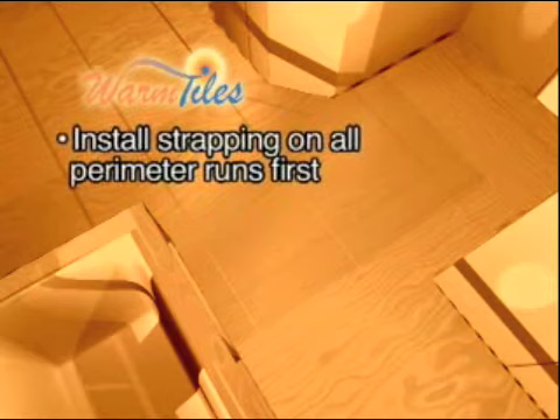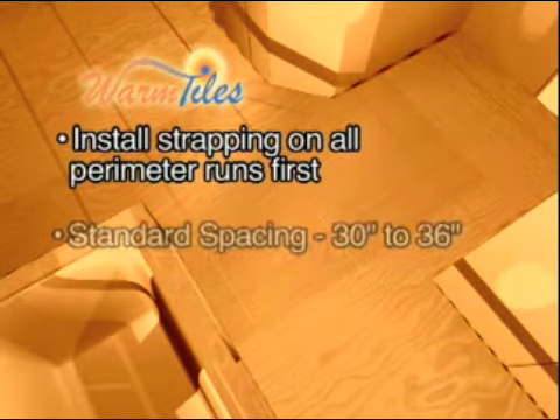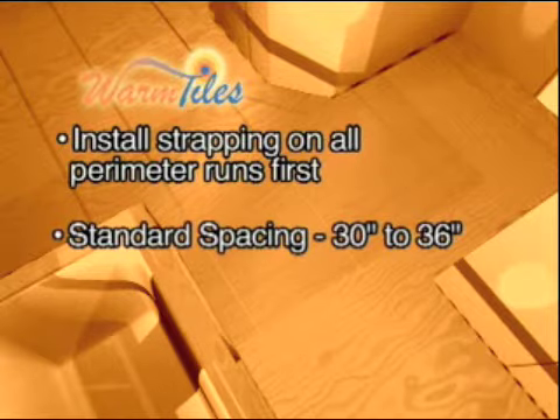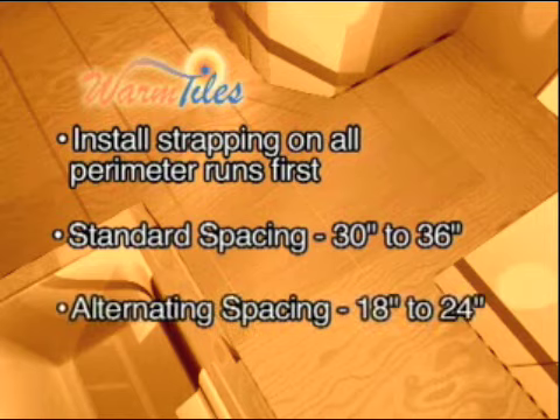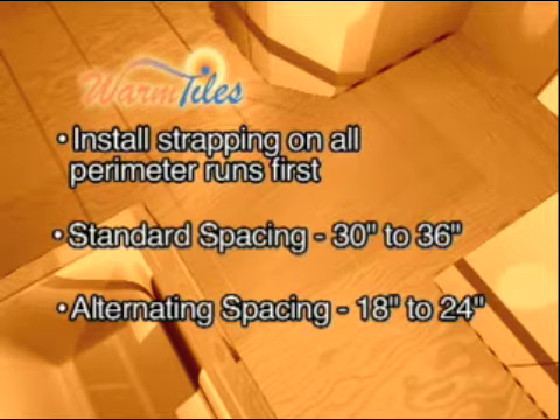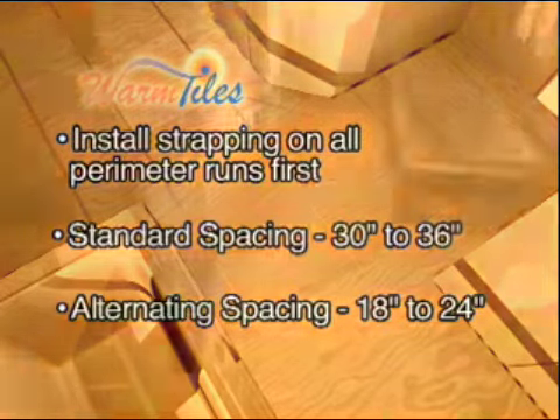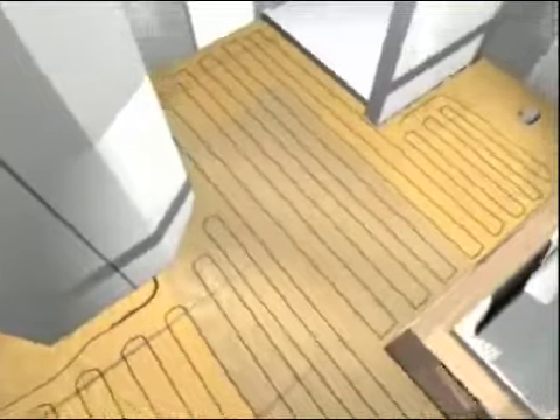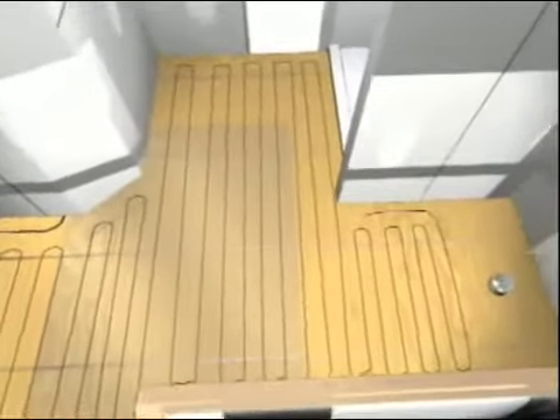Install strapping on all perimeter runs of the room first. For standard spacing, install subsequent runs of strapping at 30 to 36 inch intervals between the perimeter runs. For alternating spacing, install subsequent runs of strapping at 18 to 24 inch intervals between the perimeter runs. Then sketch a cable layout that corresponds to the strapping layout.